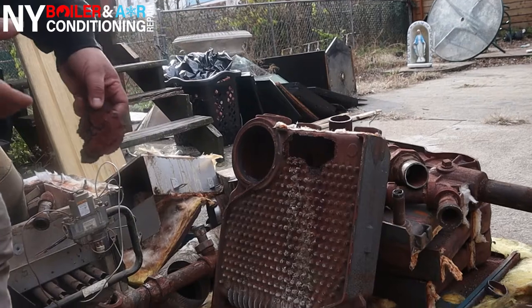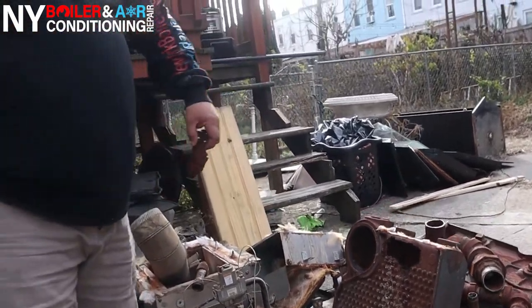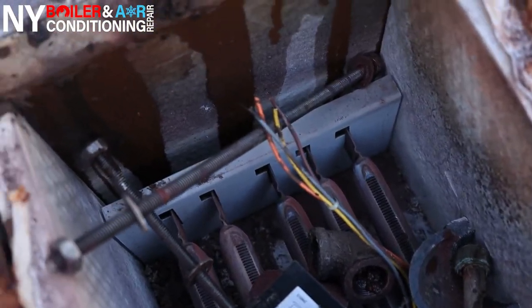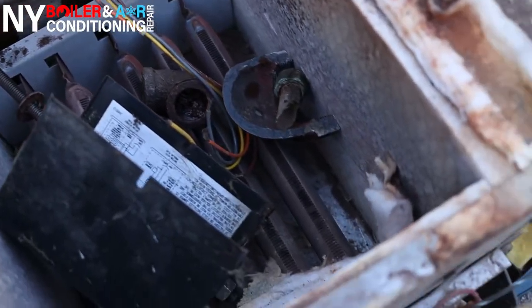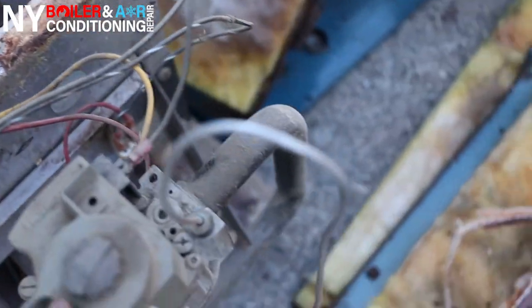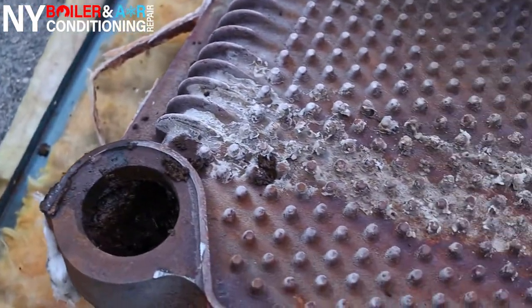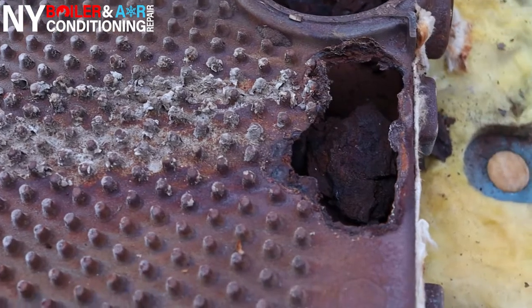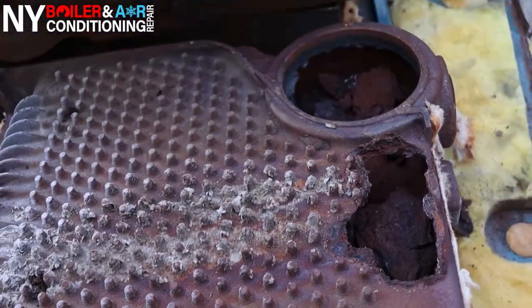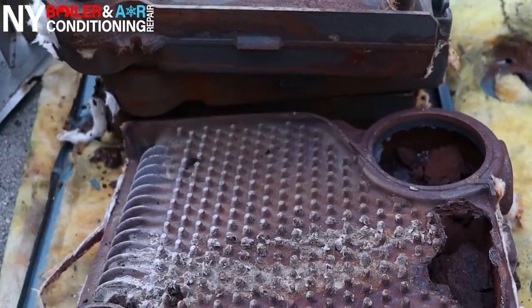So his flue pipe is his first sign of corrosion. When he called me, he said, Louis, I'm losing water, I'm losing steam pressure, some of the radiators aren't getting enough pressure or just getting lukewarm and not getting warm. As soon as I saw the flue pipe and all the rust on it, it gave me a hint, and sure enough my hunch was right. I figured he had a leak, a cracked boiler somewhere, probably on top because it's above the water line, so he wasn't able to notice it or see it.